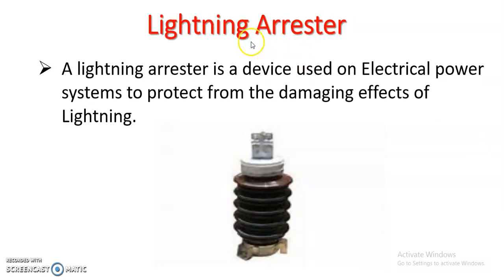Next is the lightning arrestor. The lightning arrestor is a device used in an electrical power system to protect against damage from the effect of lightning. That means if a lightning stroke or lightning surge occurs, the lightning arrestor will protect the 11 kV pole mounted substation or transformer from the lightning strokes.